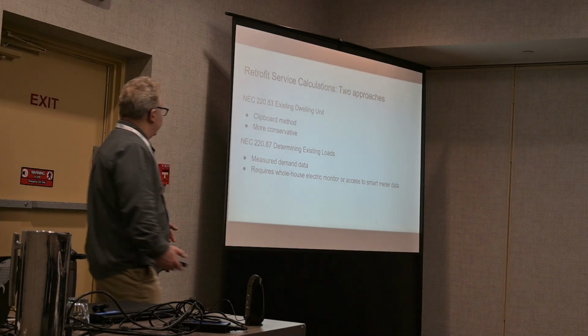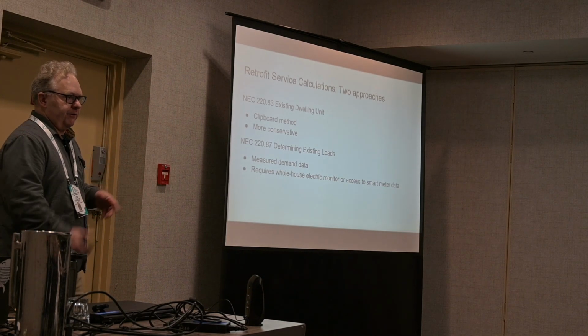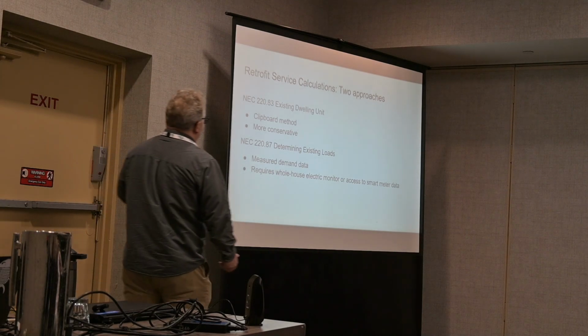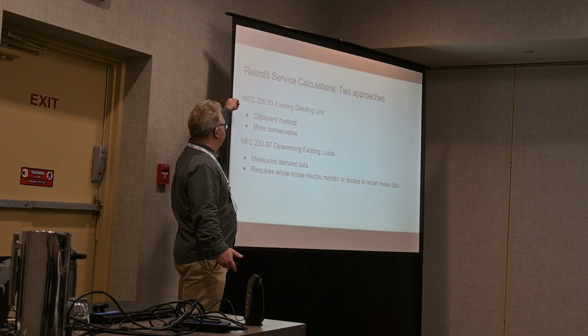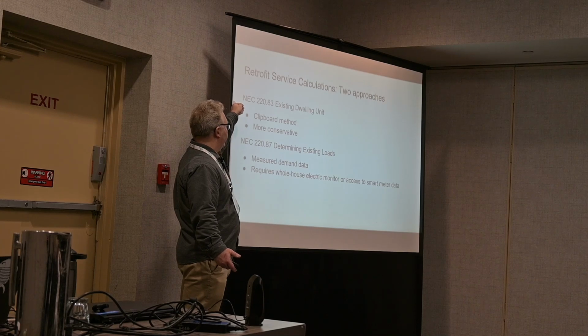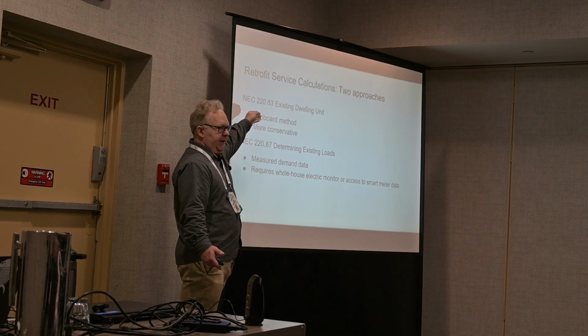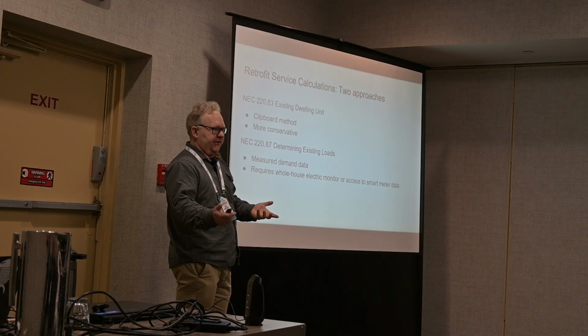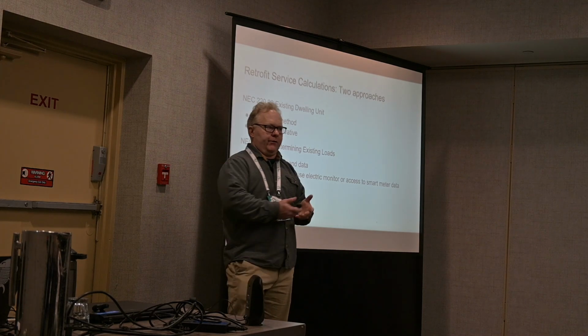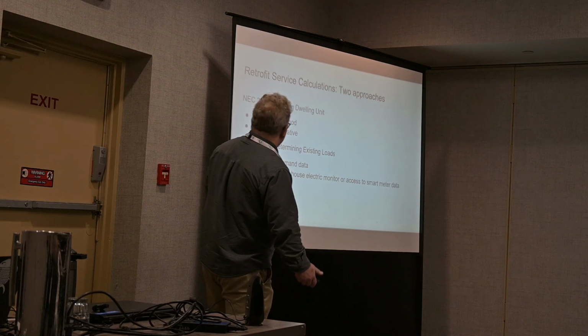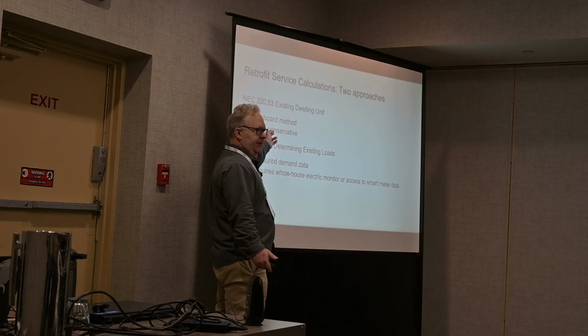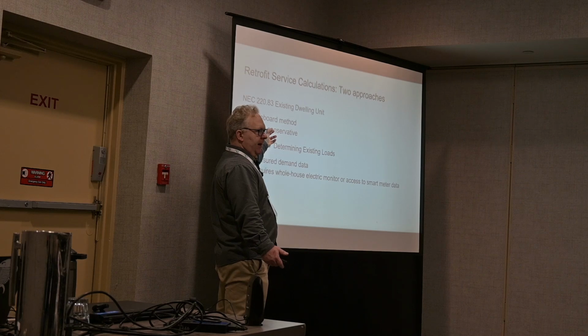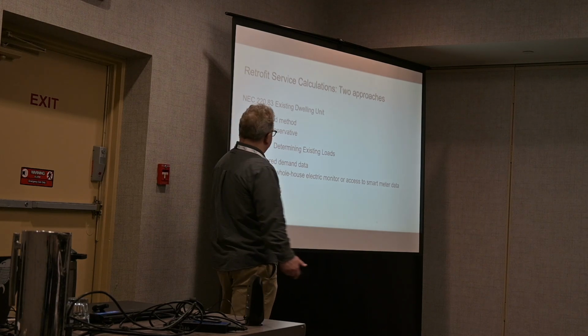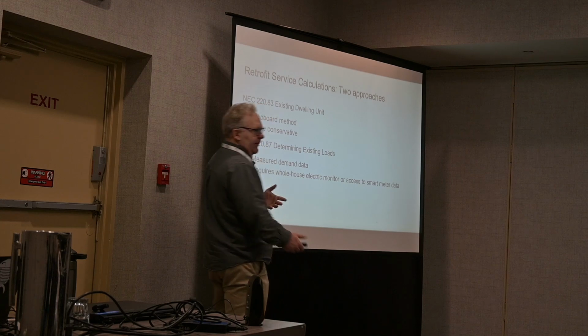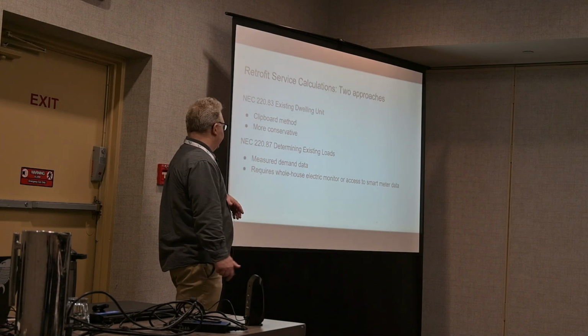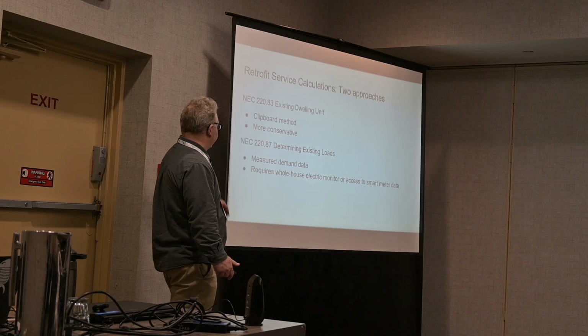The code allows for two approaches to determining whether an electric service upgrade is needed. Most of the time, we're going to be using the one that's described in NEC 220.83. It's a clipboard method, involves data collection on site, and then a quick run through a spreadsheet. It tends to be slightly more conservative, in that it's more likely to trigger a panel upgrade. But I'll show a case study that shows that these two generally deliver pretty comparable results.